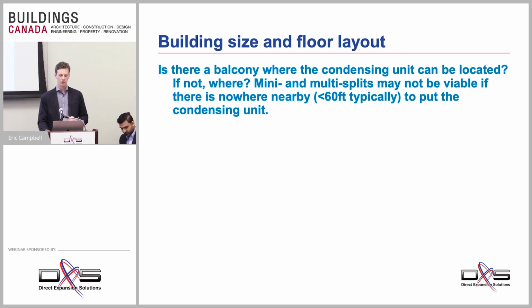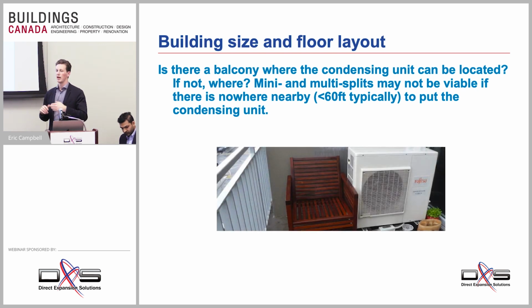In terms of building size and floor layout, if we're looking at multi-splits, the decentralized system, versus the centralized VRF system, there are differences in terms of pipe lengths. There are limitations on how far the outside condenser unit can be from those indoor units. Typically, our lowest cost solution, and I'll get to this in a little bit, will be a multi-split or a mini-split solution. But there are a couple of considerations. You need some space to put that outdoor unit, typically within around 60 feet of the indoor unit. If you have no space close enough for that condenser unit, then unfortunately we're not going to be able to look at this multi-split solution.